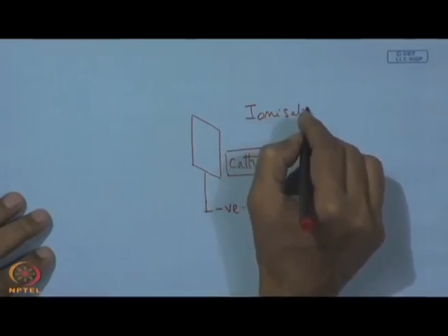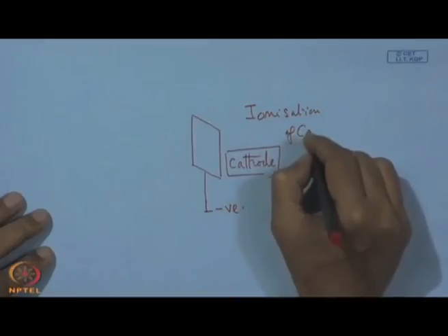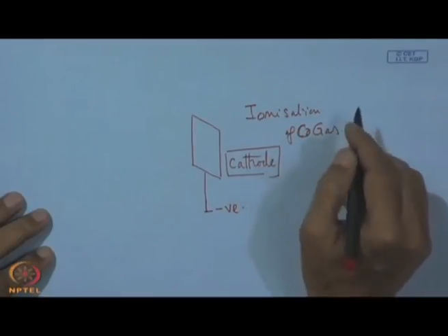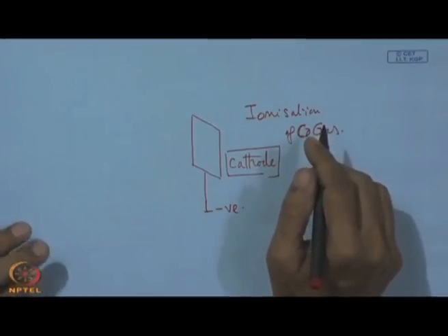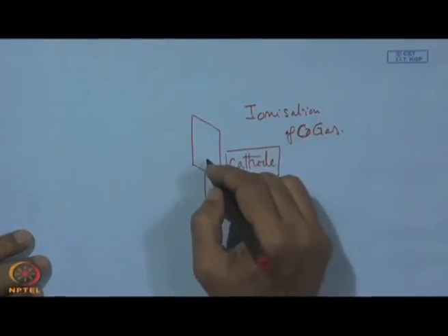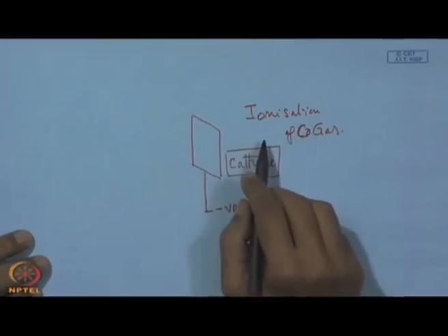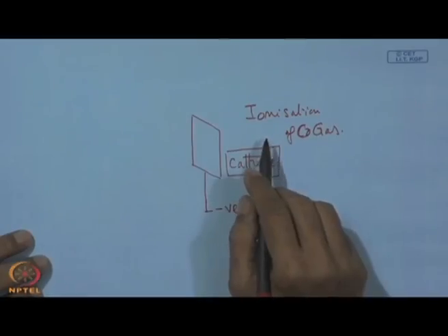So, it is actually ionization of the gas, followed by attracting these ions in a directional manner by putting one electric field. That means, here these ions will be attracted electrically by this plate, and by that there is movement of gas molecules, gas particles, not just as a neutral, but like an ion, and this is in principle known as the ion pump or ion pumping. So, these are attracted by this cathode.